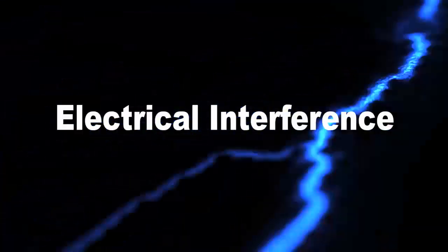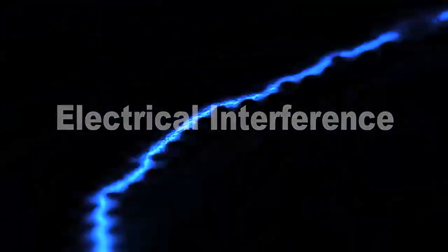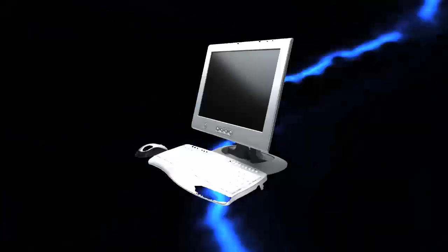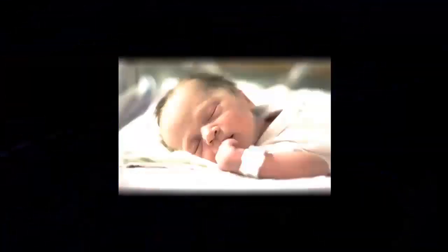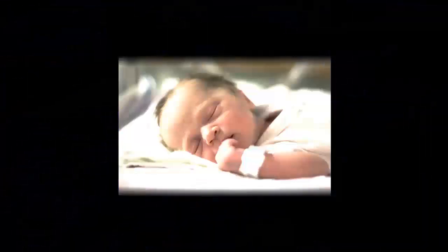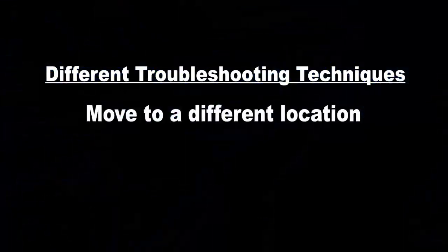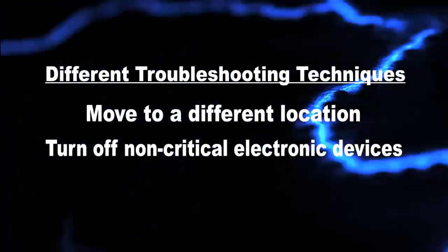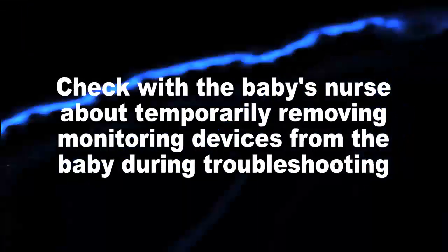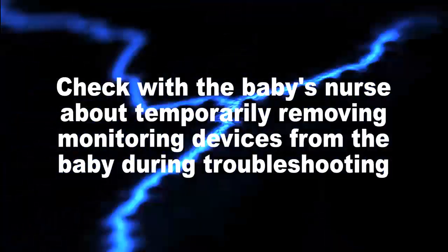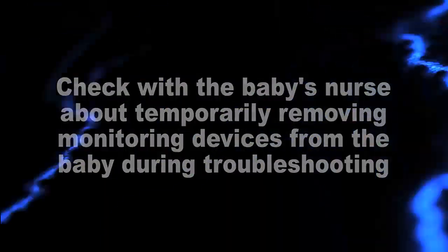Electrical interference in the test environment can be difficult to identify. It can be caused by cell phones, other computers, large monitors, RFID tags on the baby, or other monitoring equipment attached to the baby, or nearby X-ray or MRI equipment. When electrical interference occurs, it may take trying different troubleshooting techniques to discover the source. Moving to a different location, turning off non-critical electrical devices is suggested. Of course, you'll need to check with the baby's nurse or doctor to determine whether other medical devices attached to the baby can be temporarily disabled or removed.